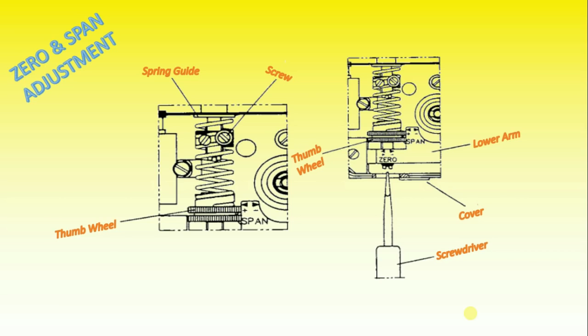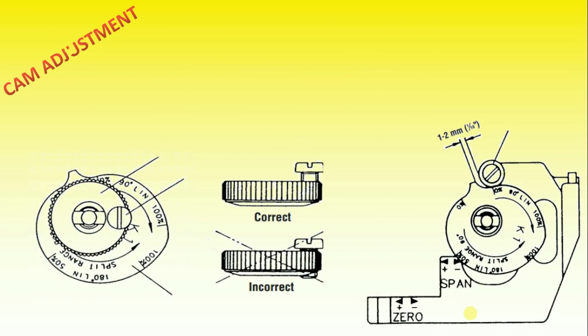Now, how to adjust the cam in pneumatic positioner. With the cover and indicator removed, loosen the screw and turn the cam locking nut counterclockwise until the cam loosens. Adjust the cam as desired, making sure that the ball bearing always is riding on an active lobe on the cam.